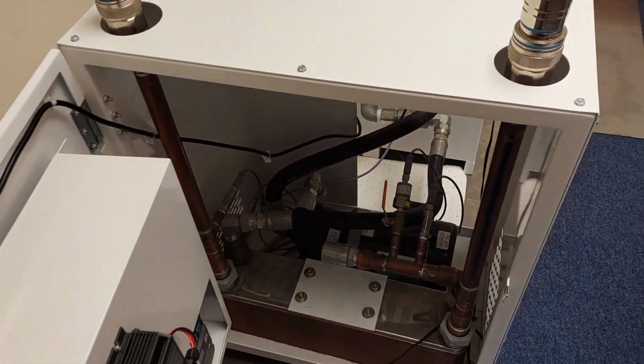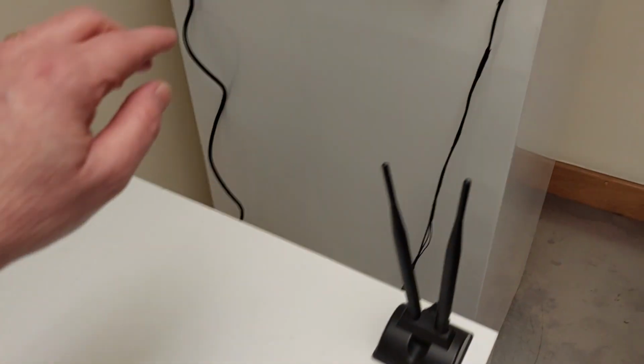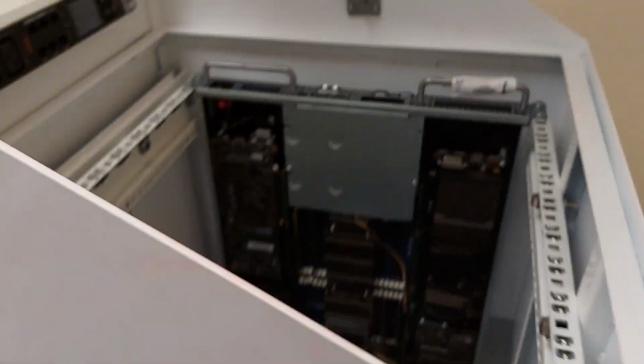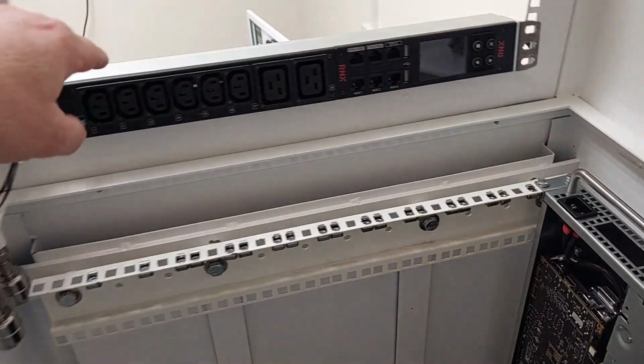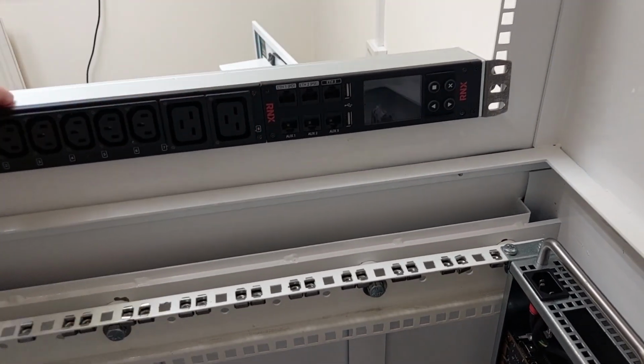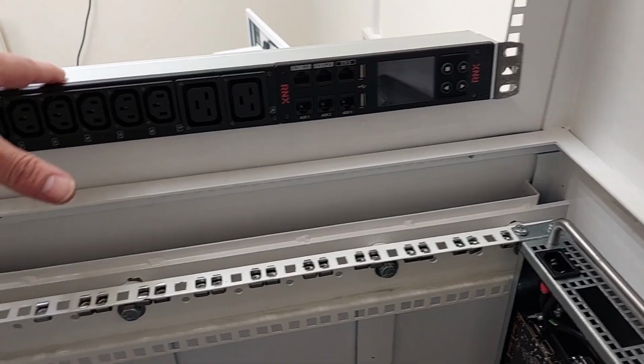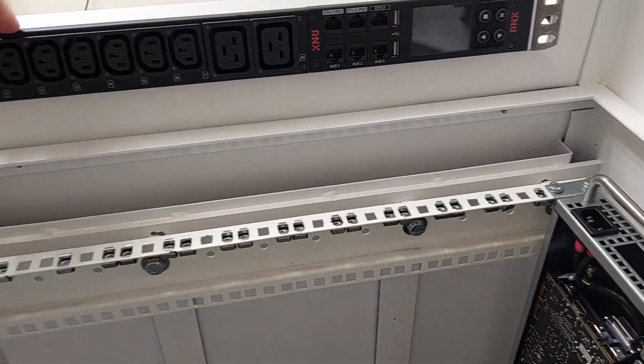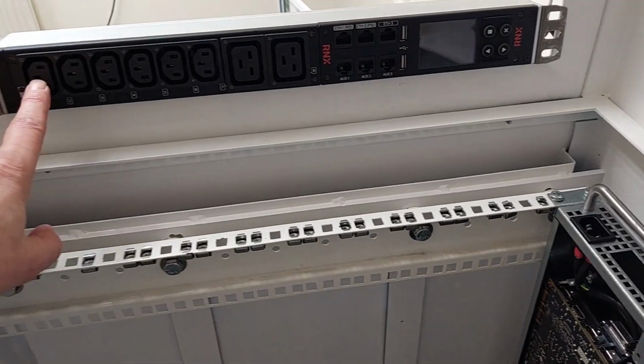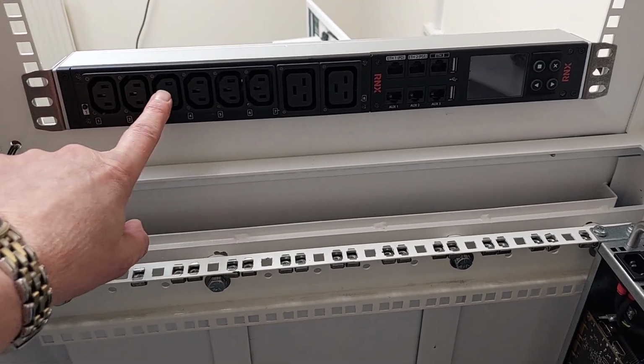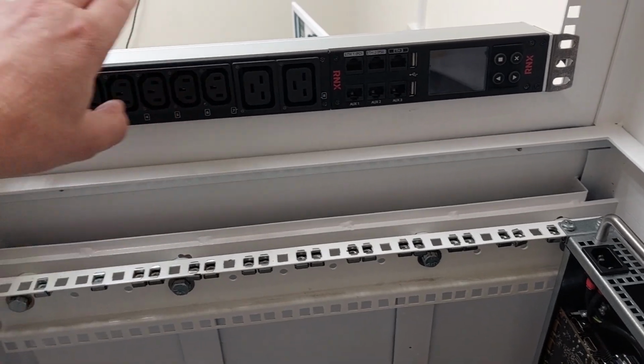What we're also using Velocity to do is talk to the smart intelligent PDU. From here we can ascertain what current we're drawing externally into this unit, into the immersive chamber unit, to fire it up, and what we're pulling on a current basis against each of the independent slots.